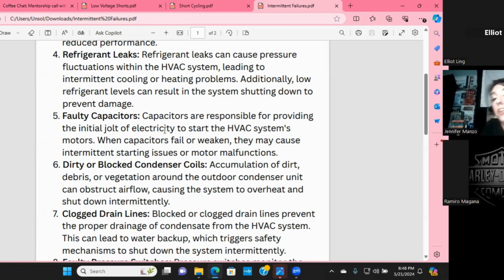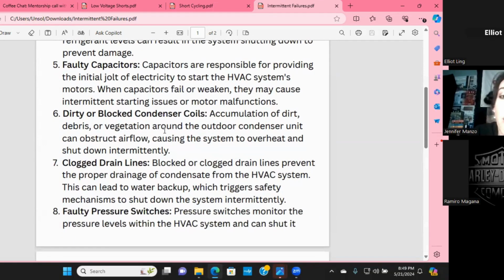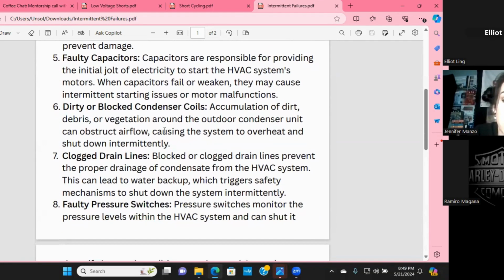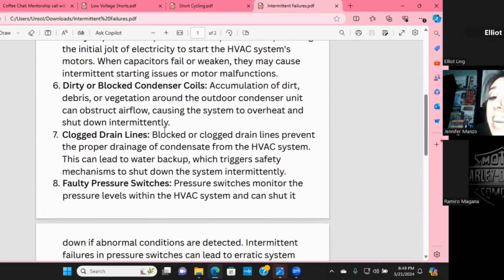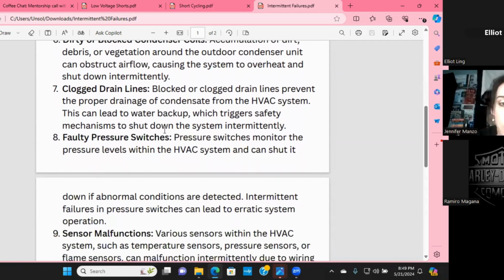But on top of that, if your capacitor is fine, it still could be a fan issue. We still have fan windings that go bad sometimes. We still have overamping. We have lots of things that can go from the capacitor that still make our jobs hell. Dirty or blocked, anything, you guys, dirty or blocked, anything. Drain lines should be 100% clear. Those of you in the South, we'll talk about drain line boogers. You get the big clog that is like the whole width and length of the tube, and you've got to blow it out with nitrogen, and you get this snake looking thing that comes out of it. That is detrimental to your HVAC system. It might seem like a small thing, but drains are just as important as any other component.